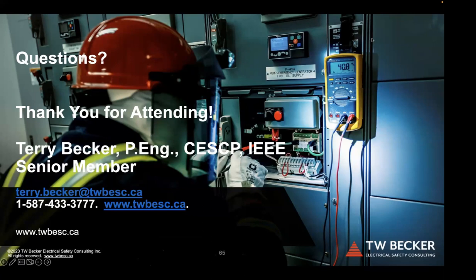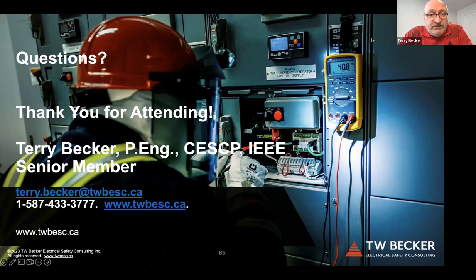The first question I have is, is arc flash only possible on three phase, or can it happen on single phase systems? That's a really good question. IEEE 1584, the 2018 edition, is the key standard for us in North America and actually internationally. It establishes 208 volt three phase as the lowest voltage for a three phase arc flash. We might get a single phase arc flash in that three phase electrical equipment, but it's instantaneously going to go to all three phases. If we have 120 volt single phase electrical equipment, it's not going to create an arc flash. You'll get an abnormal arcing fault, like the screwdriver in a panel board that the electrician created because they didn't wrap up the shaft.